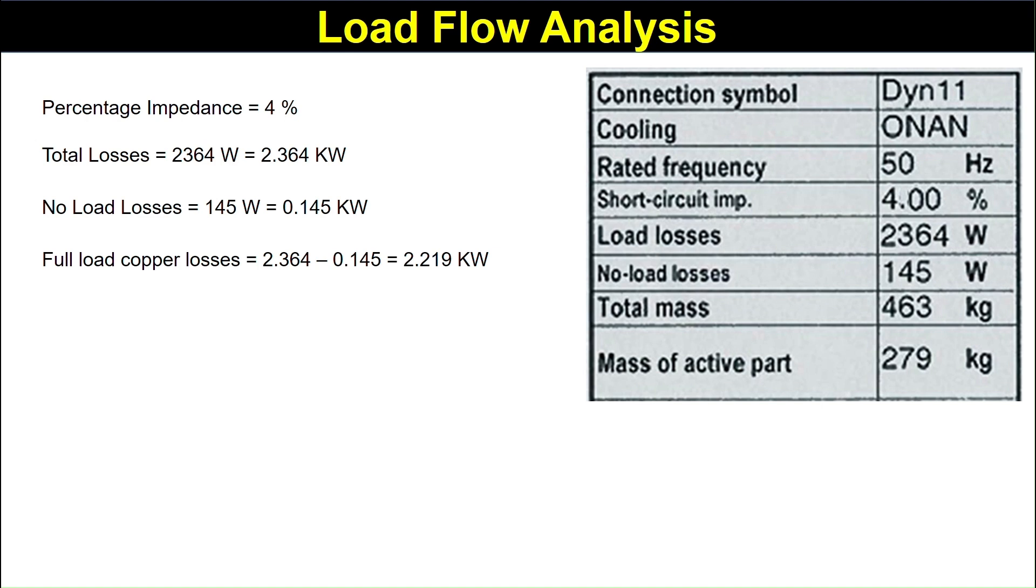Full load copper loss is equal to 2.364, that is the total loss, minus no load loss, that is 0.145. It becomes 2.219 kilowatts. Rating of transformer is 100 kVA and we will take the rating of transformer as base kVA.